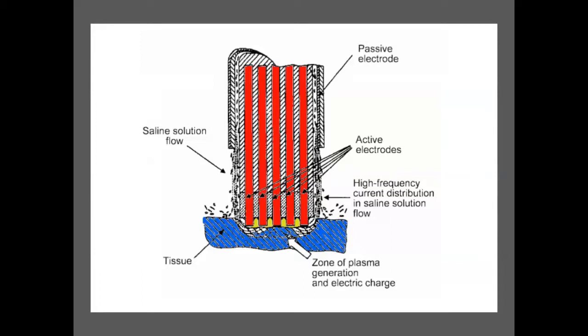Breaking down the wand: these are the active electrodes, and saline comes in here. When the saline reaches this part, the radio frequency energy from the console contacts the electrodes and you start developing the plasma. This diagram tells you that you're using plasma to do your procedure — hence coblation is a non-touch technique.